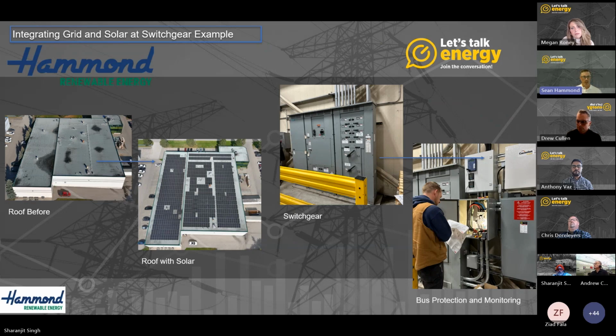So we looked at the customer's annual usage and determined that the whole roof filled with solar would cover about 40% of their annual requirements. So we figured the whole roof could be used if the other criteria were met. We did a survey on site. They have an existing switchgear with a 1,000 amp bus and an 800 amp main breaker. There are code requirements around connecting generation to switchgear, which meant we'd be able to connect a maximum of 400 amps of generation up to 600 volts. So that might be a limiting point.